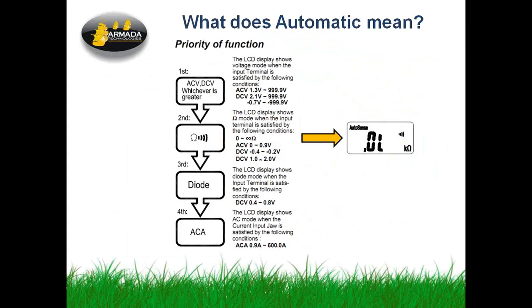This little blurb here that shows you something about how automatic works is out of the manual, and I'm not going to go through it in great detail, but it sort of explains what you commonly see on the screen when you first turn on one of these meters. The meter is constantly looking to see what it feels on its connected leads and in the clamp, and depending on what it feels from those different circuits, it switches modes. And if the meter is just there with nothing connected to the leads and no clamp around a wire or anything, it switches back to resistance and just kind of sits and waits.